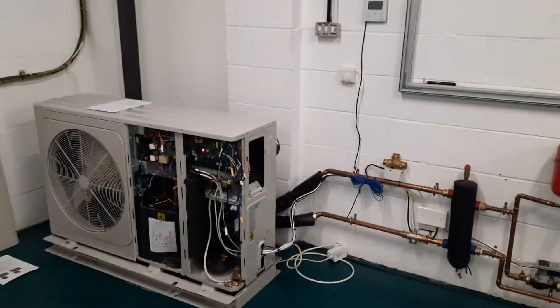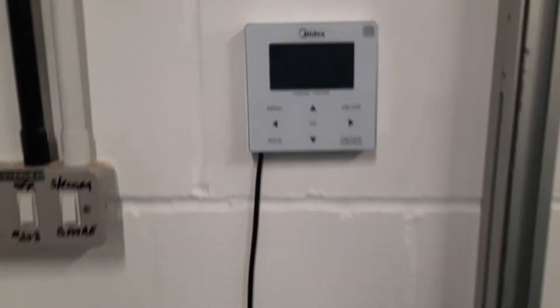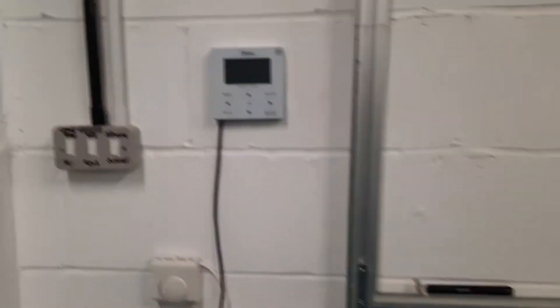In this video, I'm going to talk to you about fault code P3 on a Midea air source heat pump. P3 is a very difficult fault code to simulate. If it did come up, it would show on the screen here saying that there is a compressor current problem.